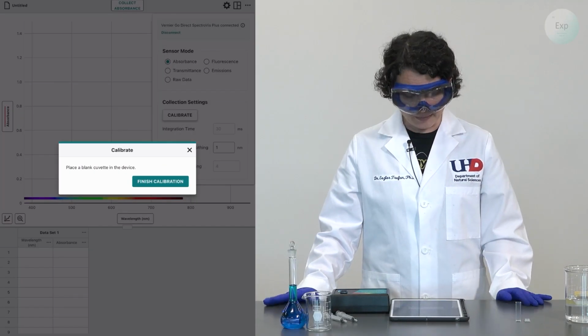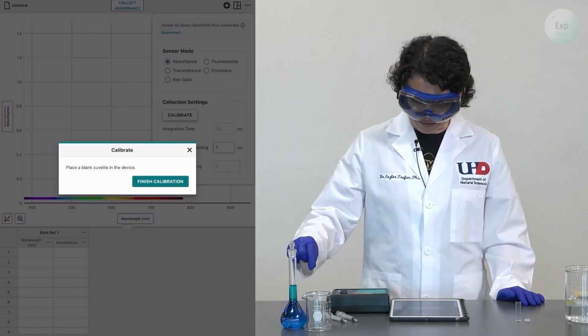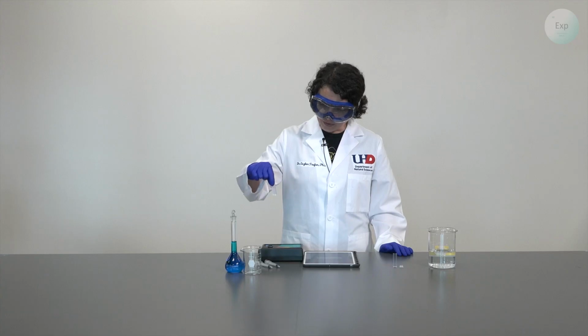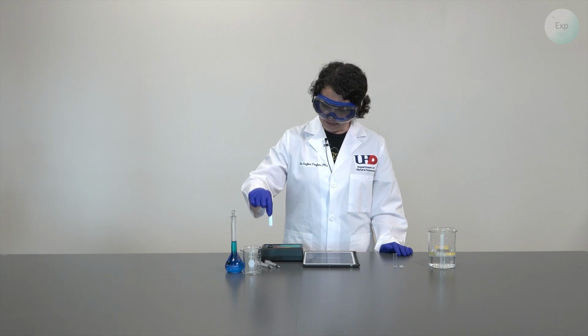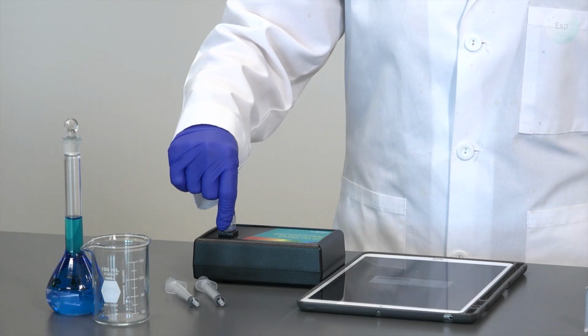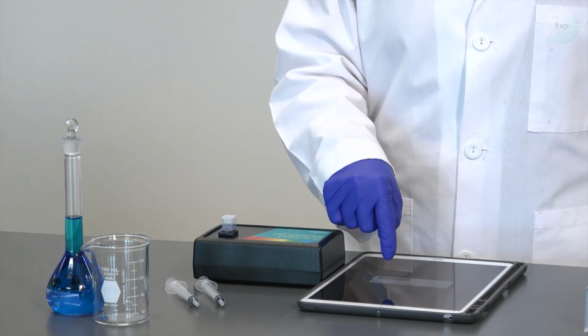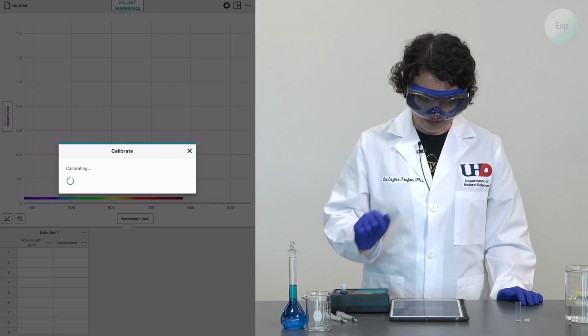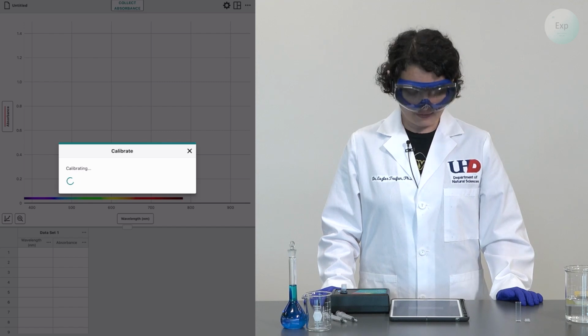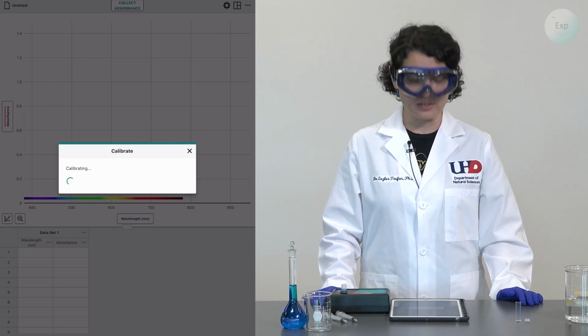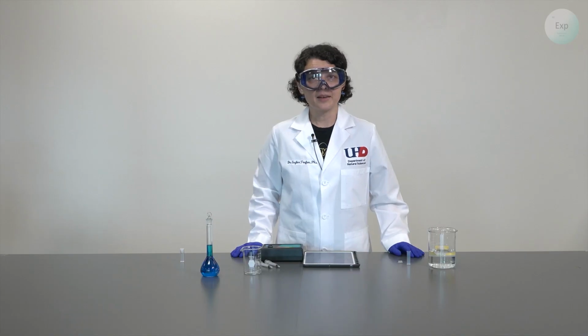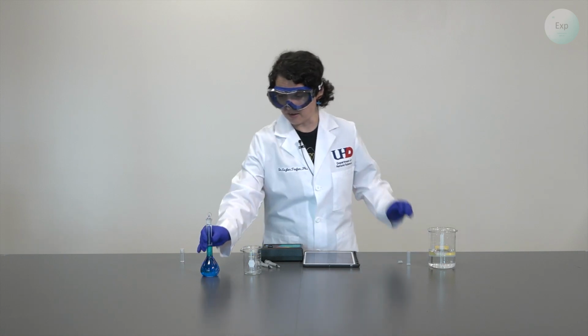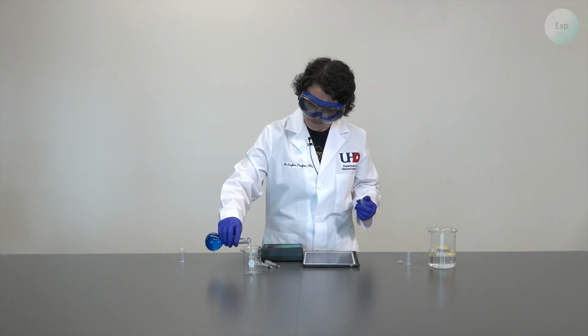Once the lamp has warmed up, it will tell us to place a blank cuvette into the device. We're going to place the cuvette with the clear sides pointing towards the white arrow and the white light bulb. At that point, on our connected device, we're going to press Finish Calibration, and it will indicate that calibration is ongoing.